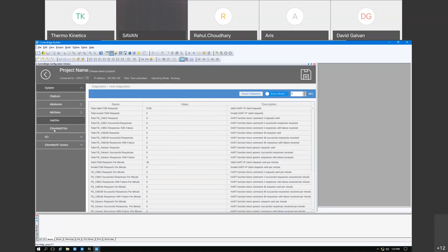Again, the PLC is here. Everything is hot swappable. These modules are hot swappable. And then one cool thing that I want to show you is the door. I'm going to walk over to the PLC itself. Right here in the front, I'm not sure if you can see it all that well, but we have an acrylic plate. We use this acrylic plate as a security boundary for your TCP/IP connection, meaning that I cannot accidentally pull out this cable. You have to take this acrylic plate off to remove the cable, which is a security factor there for accidental disconnects.